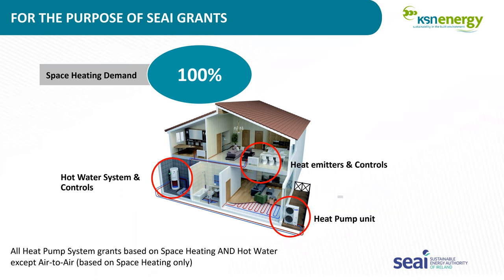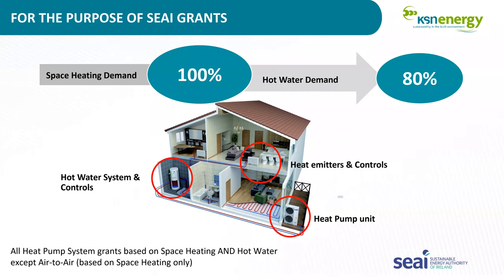The heat pump has to be able to heat 100% of the space heating on the house. That's one requirement that SEAI have. The second one as well is it only needs to do 80% of the hot water. The reason why it needs to do 80% of the hot water is heat pumps tend not to be as efficient when the temperature goes over 45 degrees. So that last little bit of heat, because of the drop off in efficiency, SEAI say, grand, if it can heat 80% of the hot water, that's satisfactory.